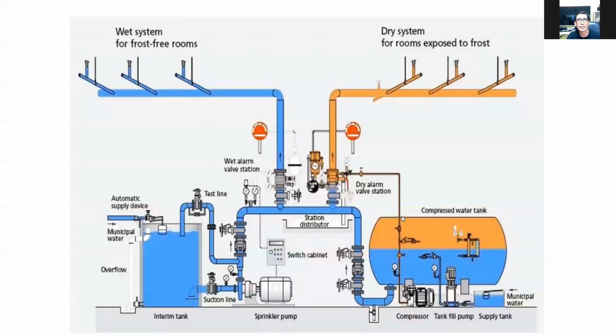So these are the different components. We have a tank and a compressor tank for the fire sprinkler system. This is the dry type and this is the wet type. For the dry type, you need a dry valve station. The fire department will connect the hose to the Siamese connected to the dry valve station, and it will trigger the pipe to trigger the fire sprinkler. In this one, there is automatic water inside the fire sprinkler system.